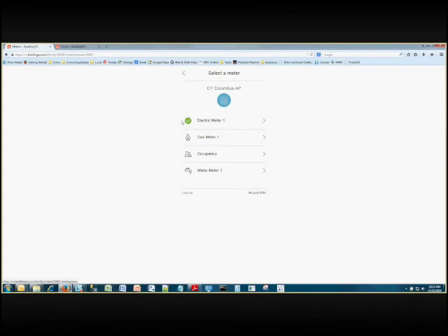Just a brief mention, when you take a meter read, most meters have what is known as a meter multiplier on it. So there's the display, and then there's a meter multiplier. What you have to do before you enter it into the system is take the display and multiply it by the meter multiplier before you enter it into the system. I'll cover that later when we go over ways of reading some common meter types, but I just wanted you to be aware.